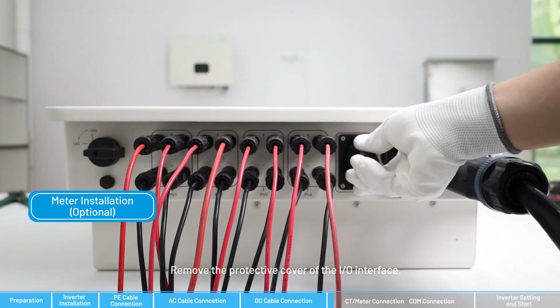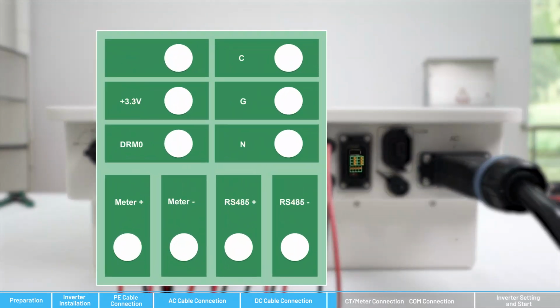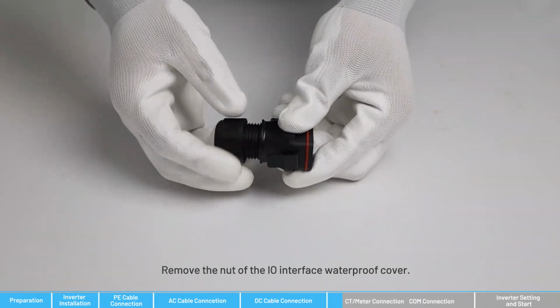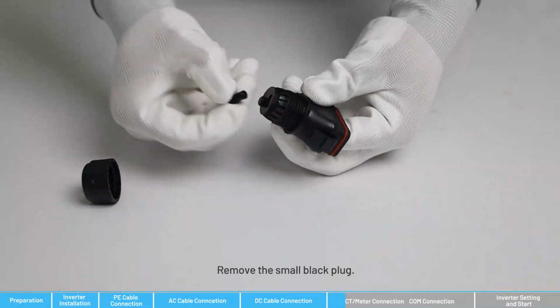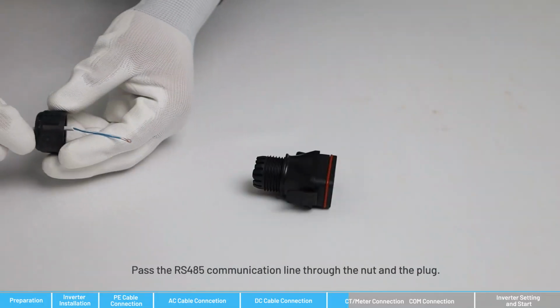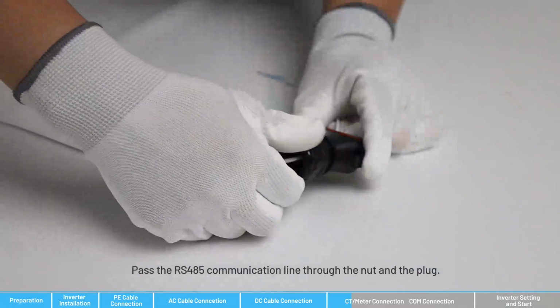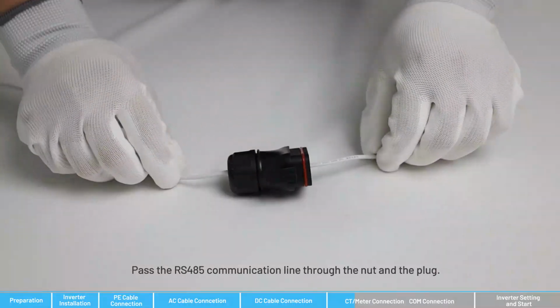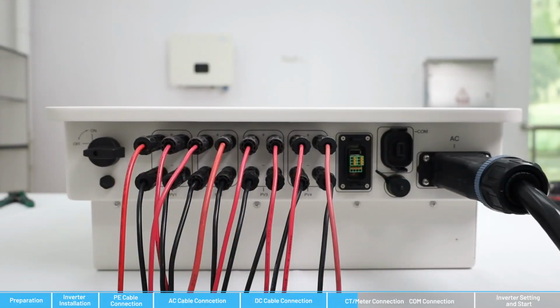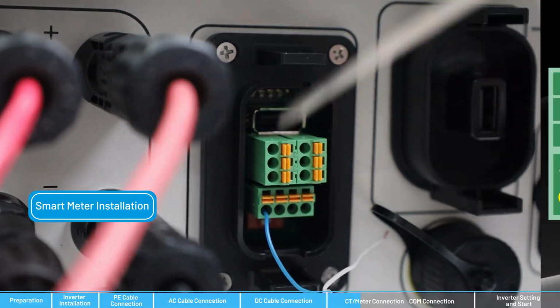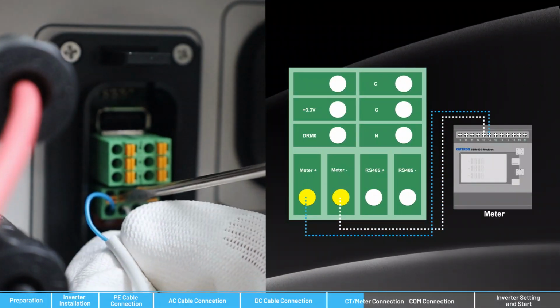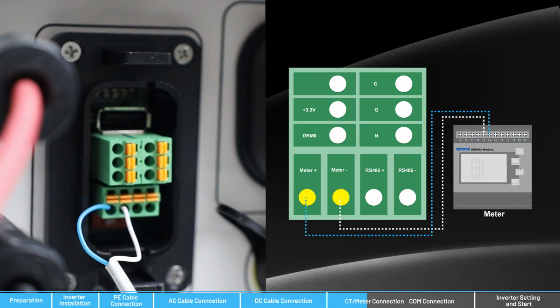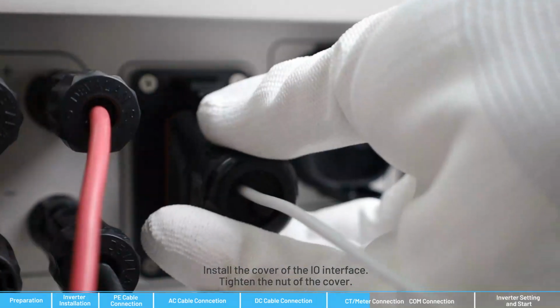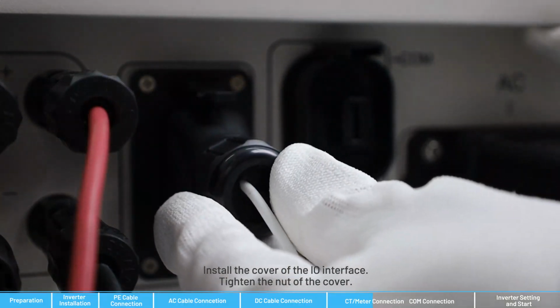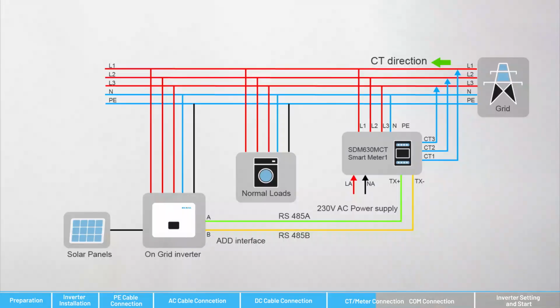Remove the protective cover of the I/O interface. Remove the nut of the I/O interface waterproof cover. Remove the small black plug. Pass the RS485 communication line through the nut and the plug. Install the cover of the I/O interface. Tighten the nut of the cover.